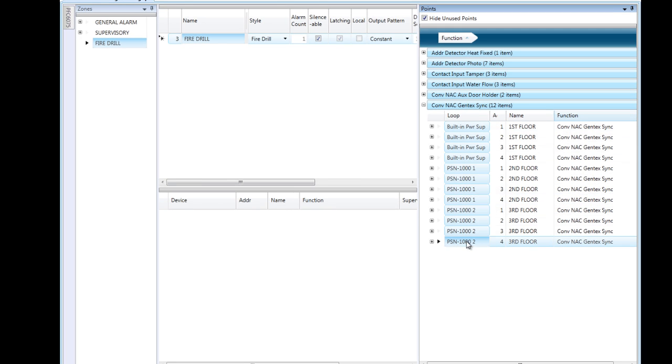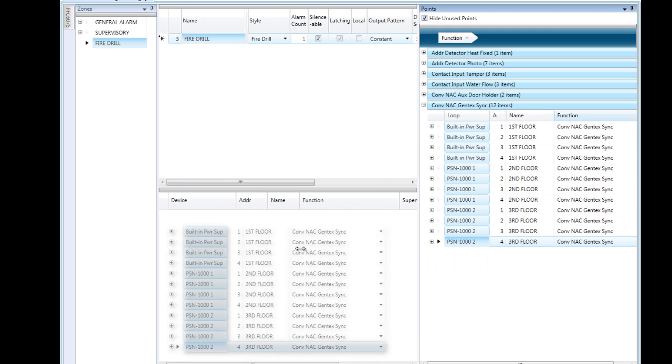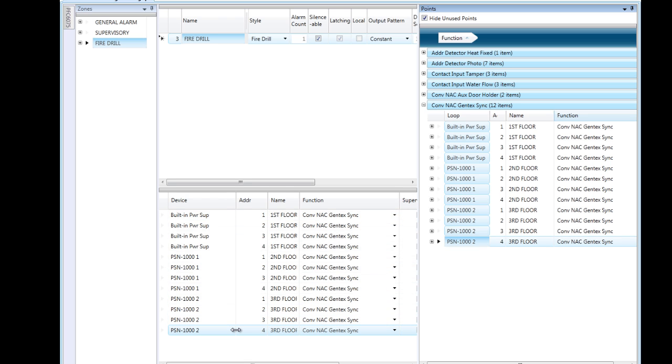So I'm going to select all of those notification circuits and drag them into the drill zone. Once I download this into the system and I press the drill button on the front of the fire alarm control panel, these circuits that are in the drill zone will activate.